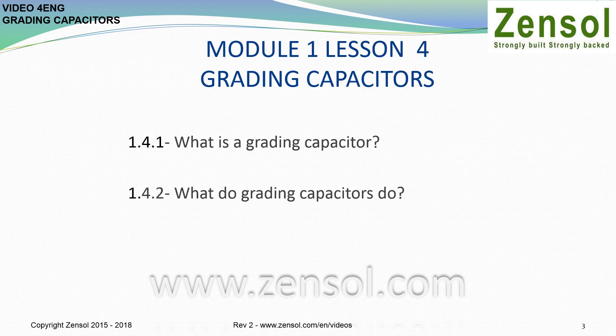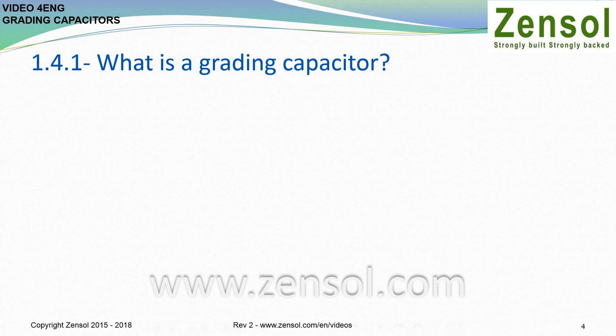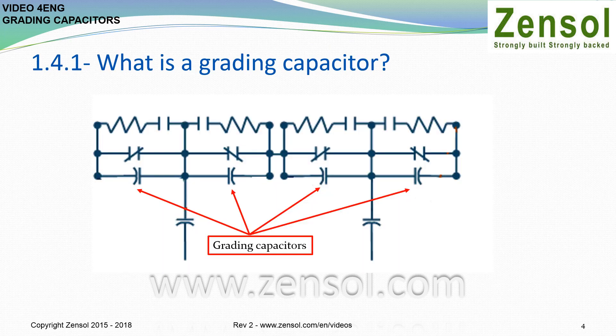Lesson 4: Grading Capacitors. What is a grading capacitor? Grading capacitors have values on the order of a few picofarads. They are mounted on circuit breakers having several contacts per pole.